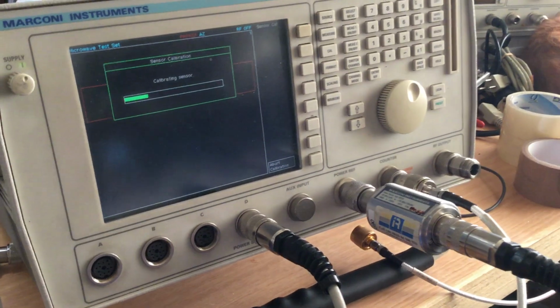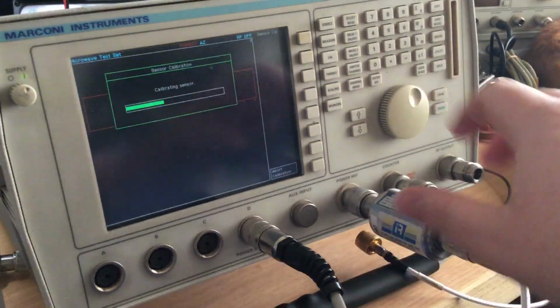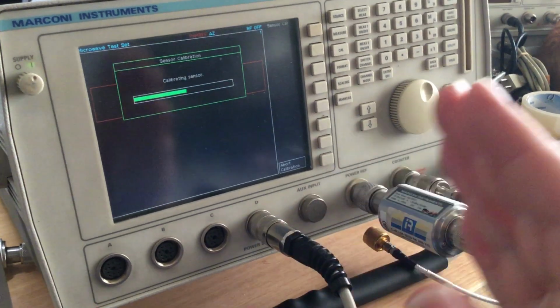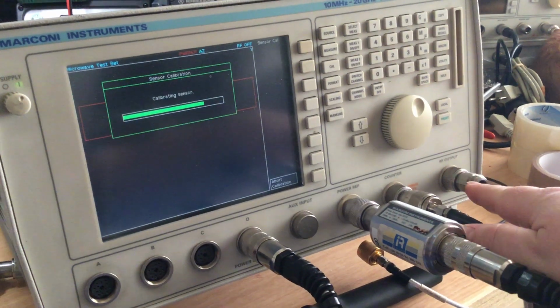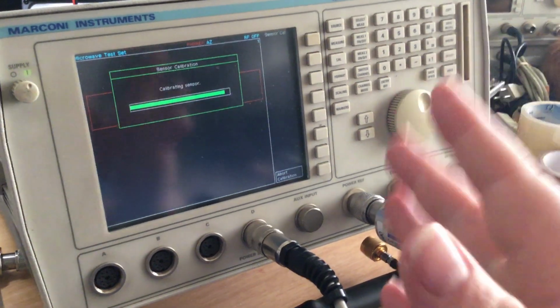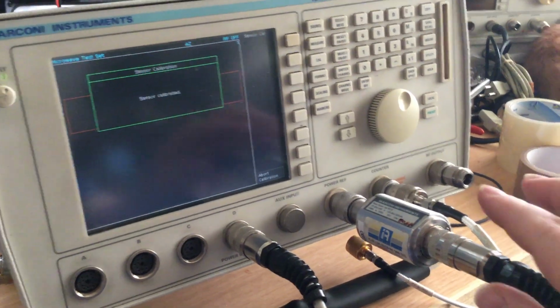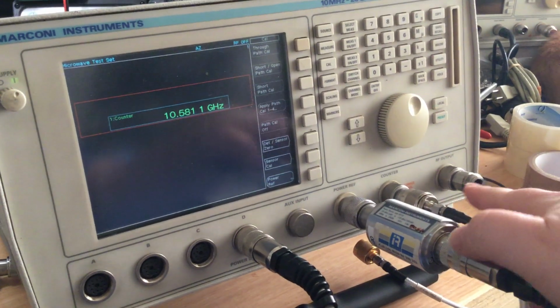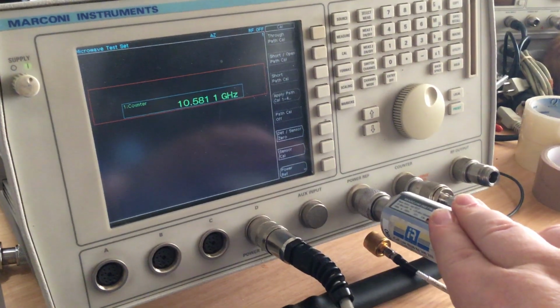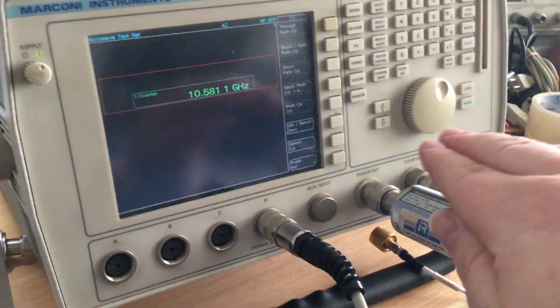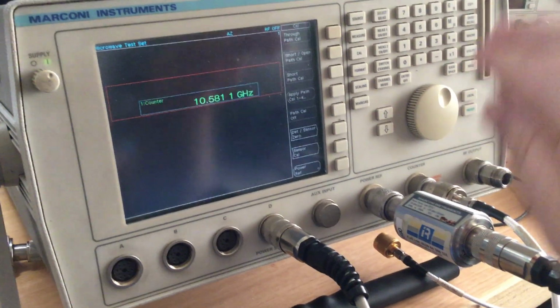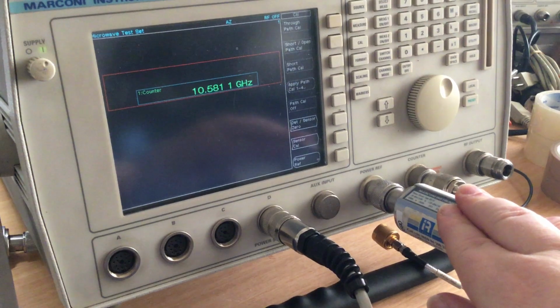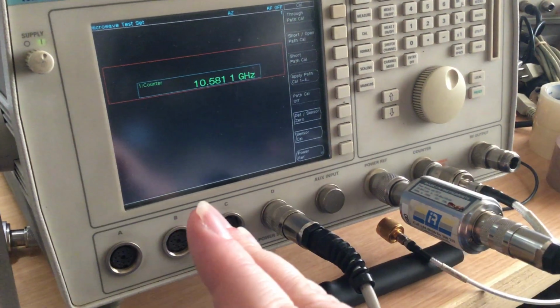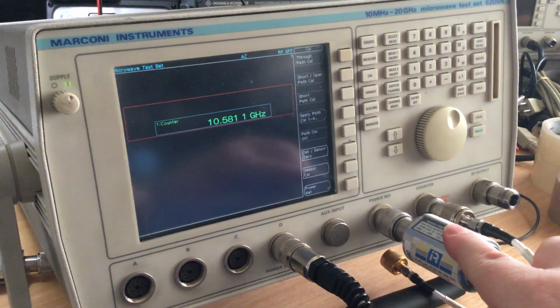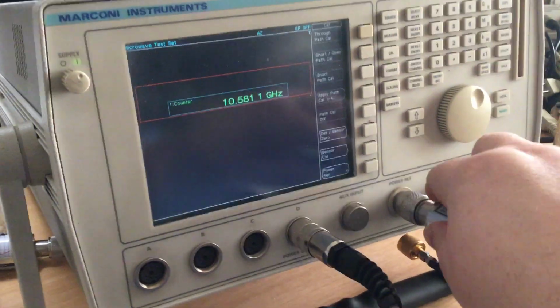And how it self-calibrates is it simply puts out, the microcontroller chooses a frequency between 10 megs to 20 gigahertz, depending on whether we do broadband or narrowband power calibration, and puts out a predetermined RF level that it thinks it should have, for example 0 dBm at say 1 gigahertz. It's looking to see if this detector, when connected to that port, can see 0 dBm at 1 gigahertz, and then it will adjust the RF levels at half a dB or 1 dB increments up and down through the dynamic range of the test set, and likewise across the entire frequency spectrum of the test set. So it can take some time to do that calibration, but that's basically what we've just done.